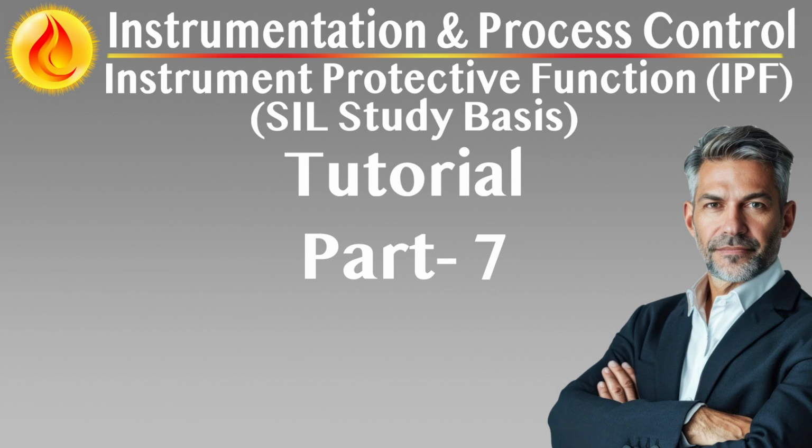Purpose and scope of automatic testing. Early fault detection. Identifies dangerous or degrading conditions before the next scheduled manual test, reduces risk of common mode or latent failures persisting unnoticed. Support for higher test frequencies. Enables continuous monitoring of key elements, effectively increasing the test coverage without increasing manual workload.